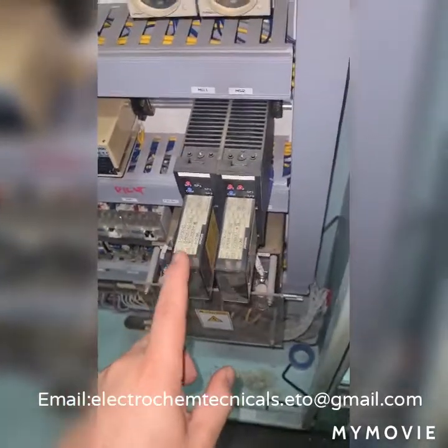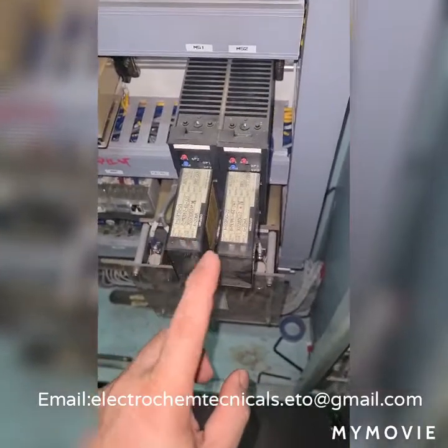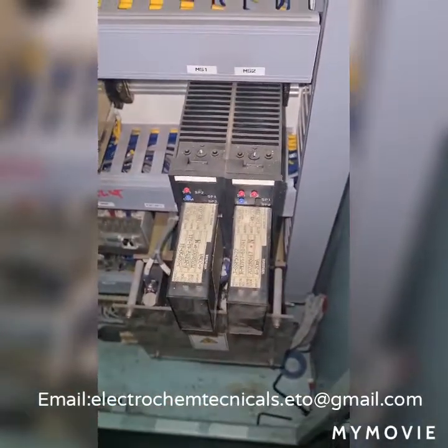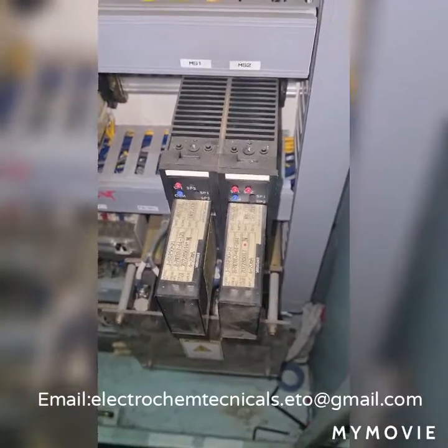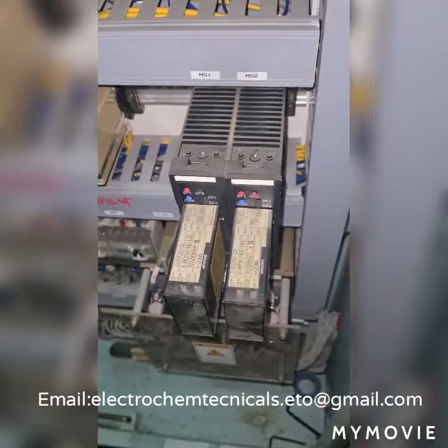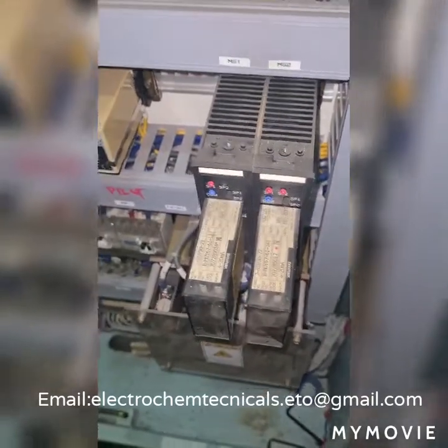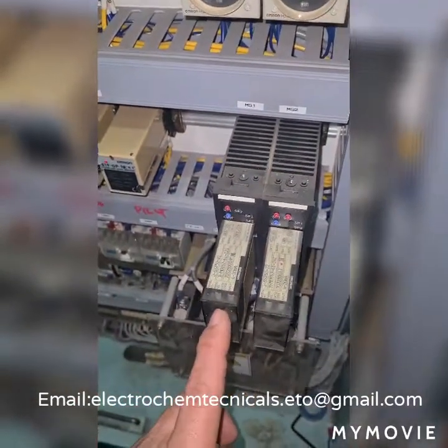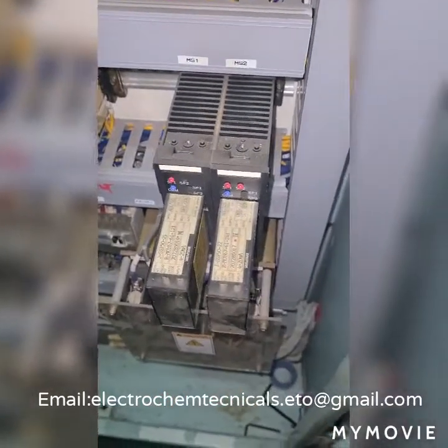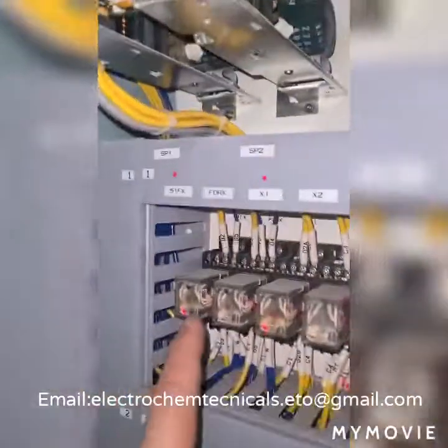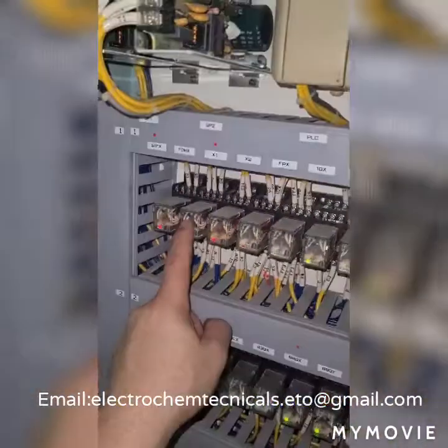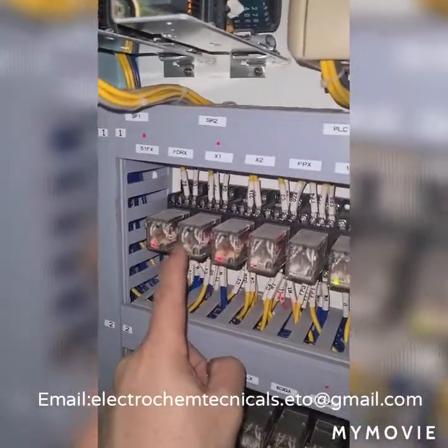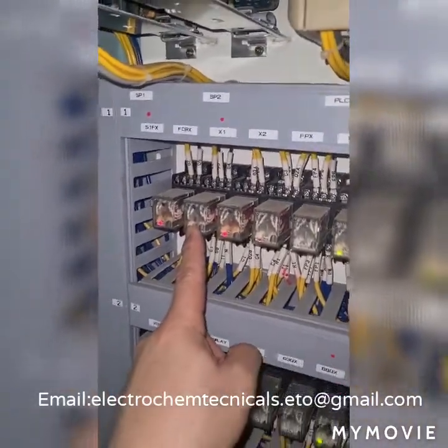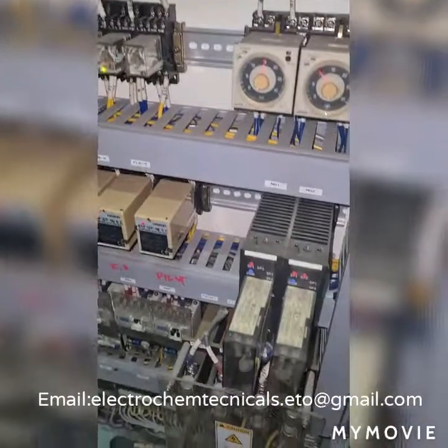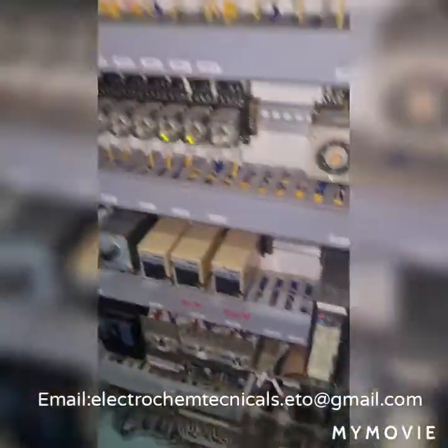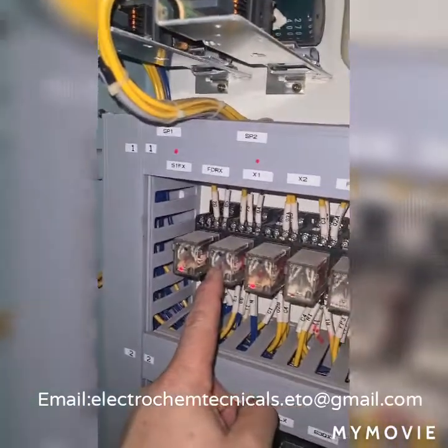This is the monitor switch from which the feed water pump will be turned on and off, and which also monitors the lowest water level. MS1 is used to indicate the water level in the engine room, and MS2 is for feed pump on and off operation. And this is the relay, FDRX. When it is activated, the feed pump will start. And if it is deactivated, the feed pump is stopped.